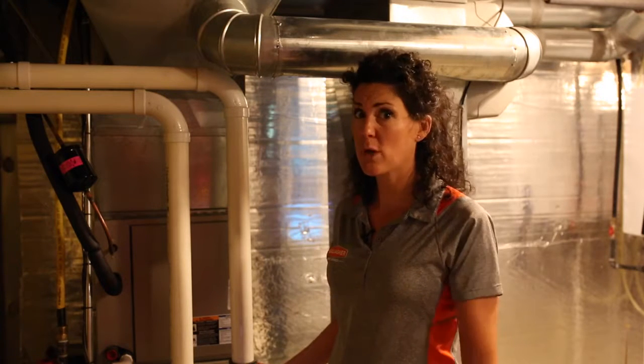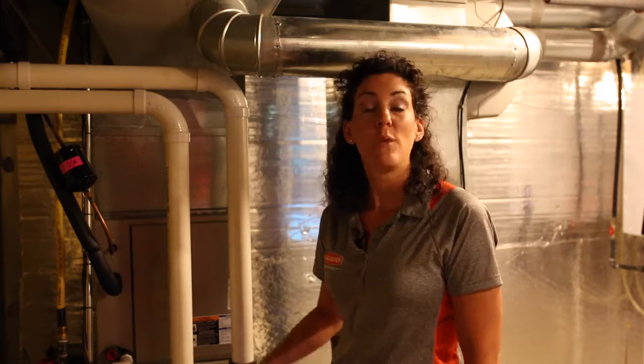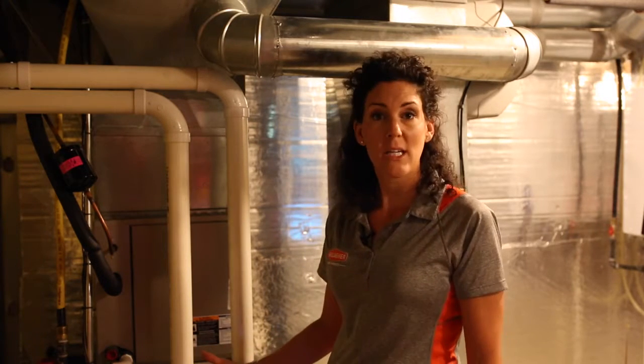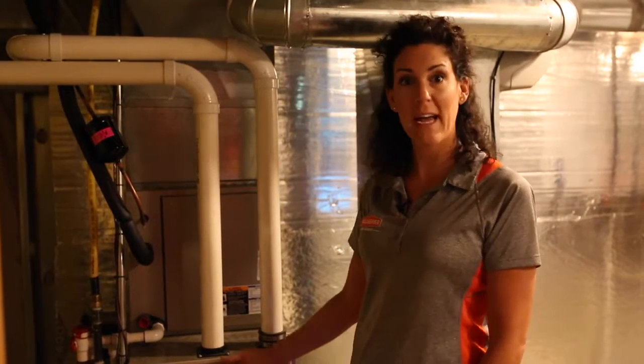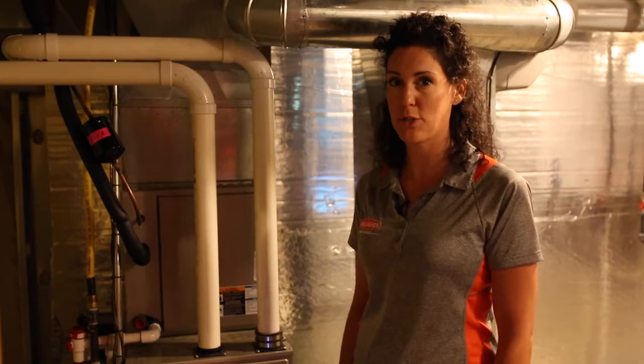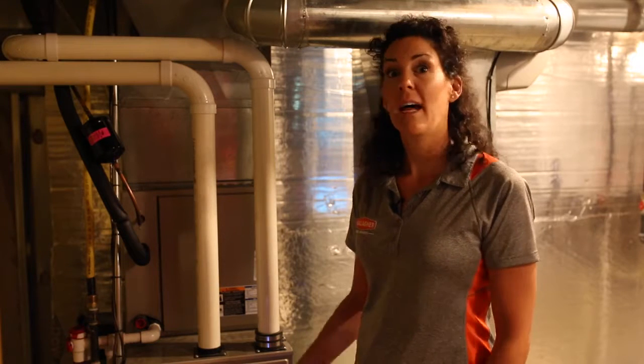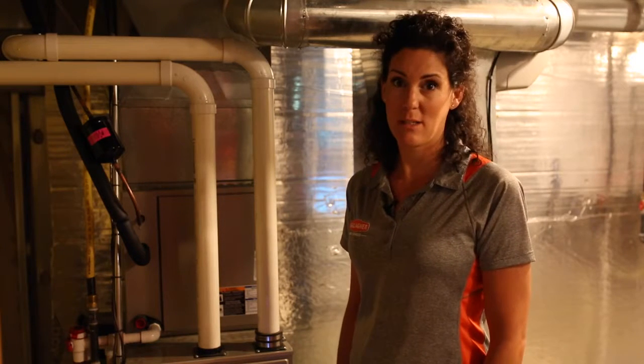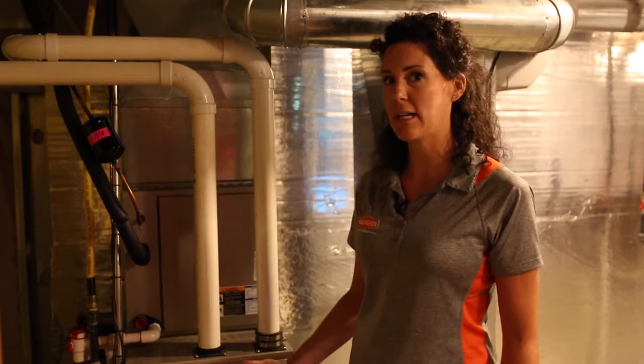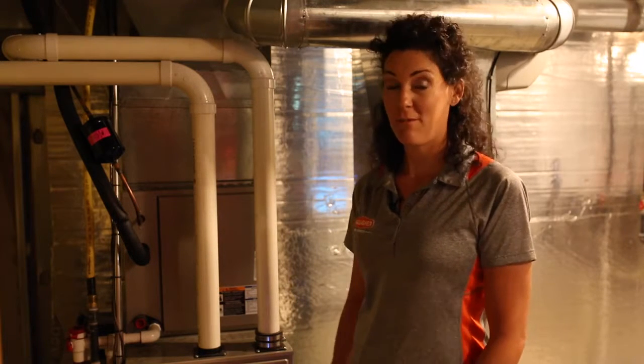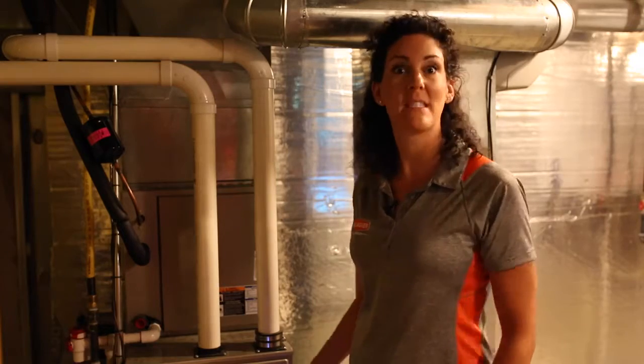One more example on the service side is during heating season, when this furnace is turned on, there's a firebox inside where the fire occurs and the heat occurs. You need air to pass over that firebox, called the heat exchanger, so that it operates at a low temperature. If not enough air is getting to that firebox, you can get a cracked heat exchanger because it's operating at high temperatures. That is a very expensive repair and can also lead to actual replacement of the system. So there's three good examples on the service side of why to make sure that furnace filter or air handler filter stays nice and clean.